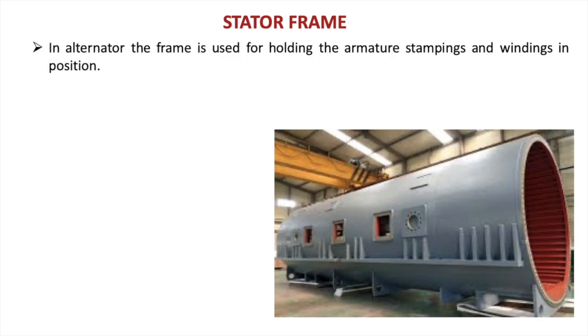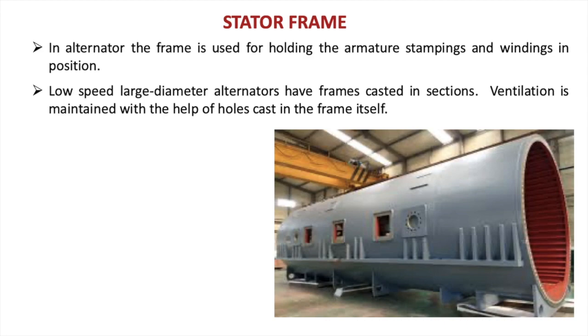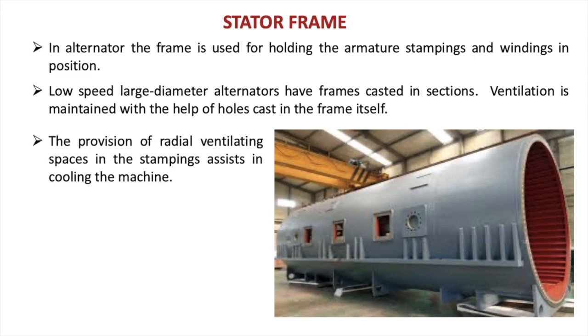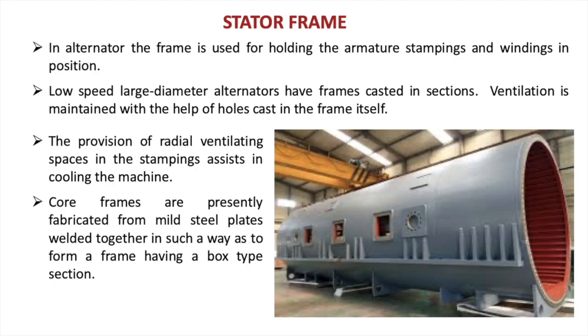In an alternator, the frame is used for holding the armature, stampings and windings in position. Low speed, large diameter alternators have frames cast in sections. Ventilation is maintained with the help of holes cast in the frame itself. The provision of radial ventilating spaces in the stampings assists in cooling of the machine. Core frames are presently fabricated from mild steel plates welded together in such a way as to form a frame having a box type section.